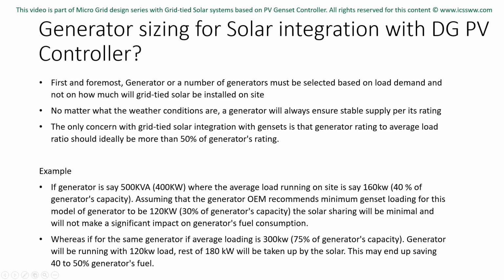For PV Genset controller integration, there is a lot of confusion around what should be the rating of generator. Generator or a number of generators must be selected based on load demand and not on how much grid-tied solar will be installed on site. Let me elaborate on this. A user maintains and operates generator backup to run load in case of grid blackout. No matter what the weather conditions are, a generator will always ensure stable power supply per its rating.